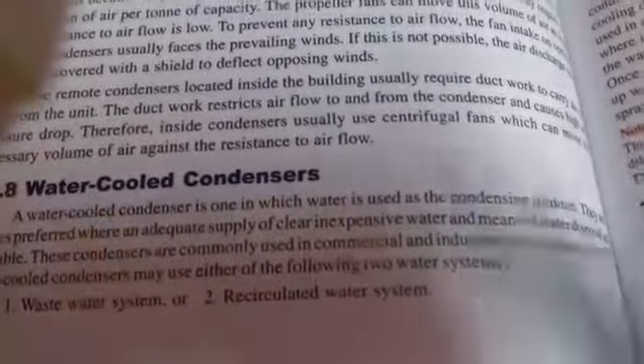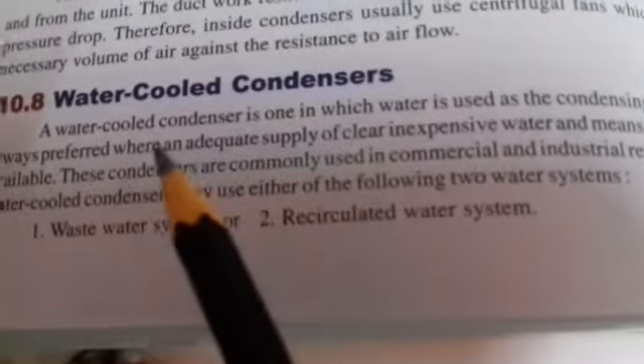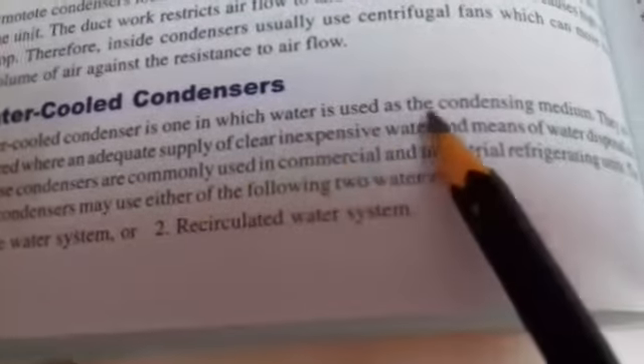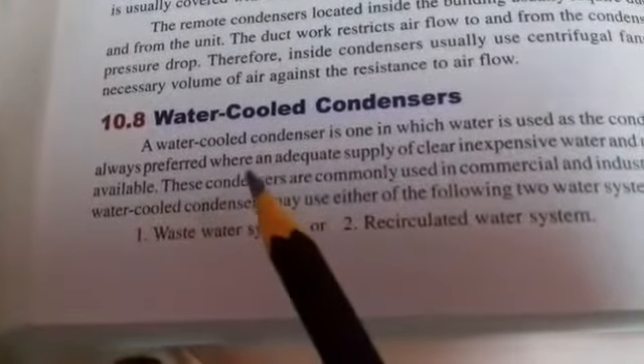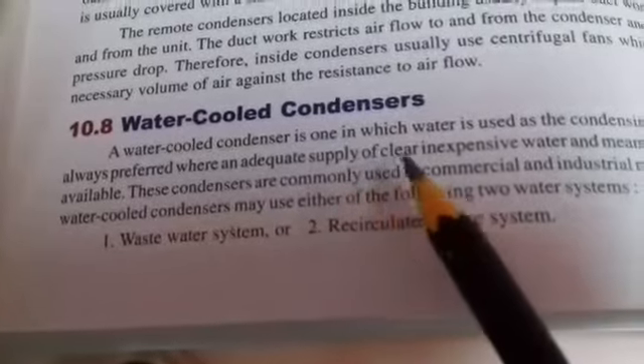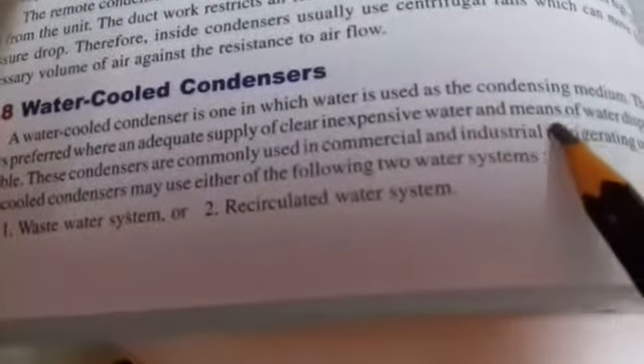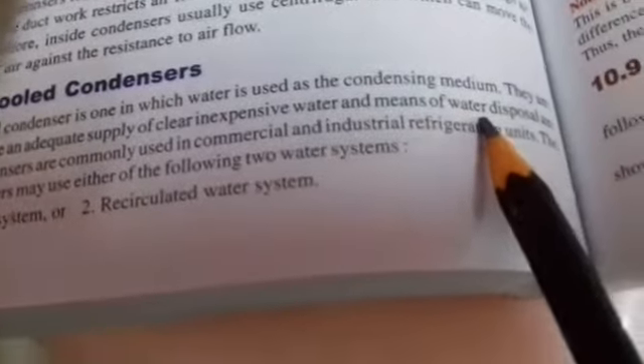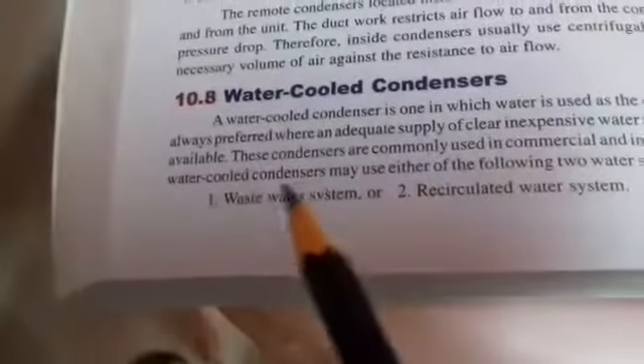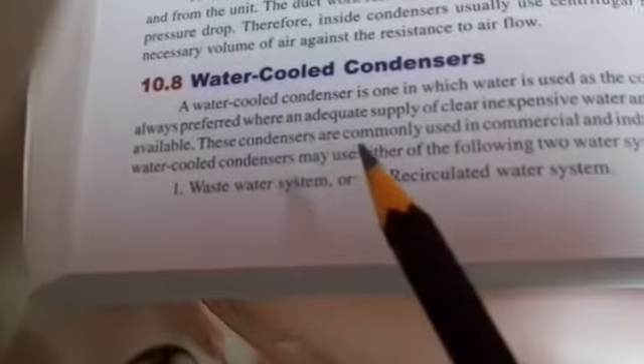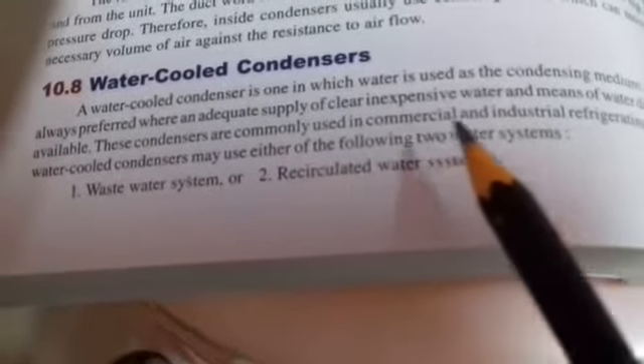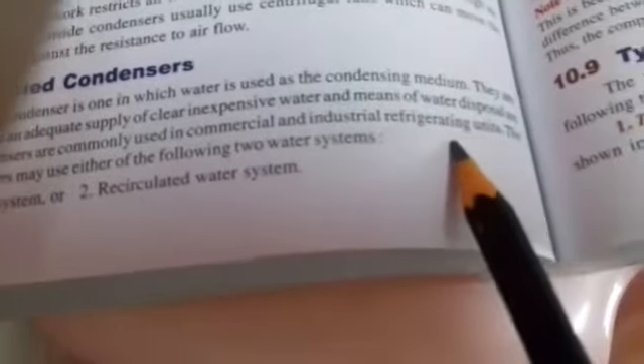So I am going to deliver a video lecture on water cooled condensers. Condensers which are very much in use for the refrigeration system. A water cooled condenser is one in which water is used as the condensing medium. They are always preferred where an adequate quantity supply of clean and inexpensive water and means of water disposal are available. These condensers are commonly used in commercial and industrial refrigeration system.